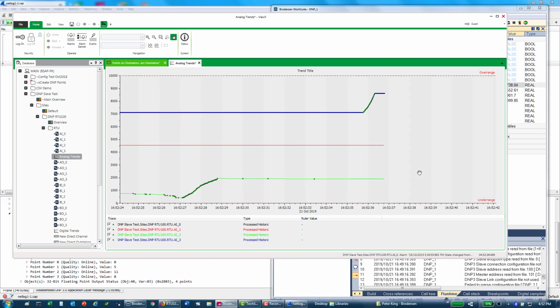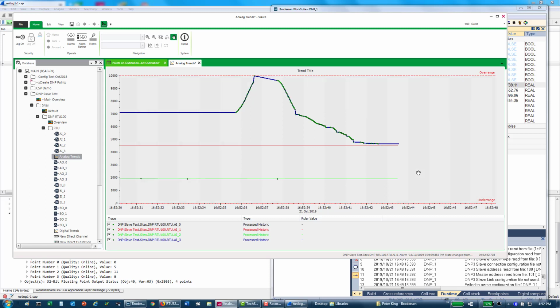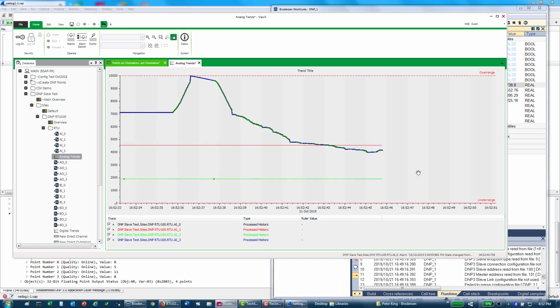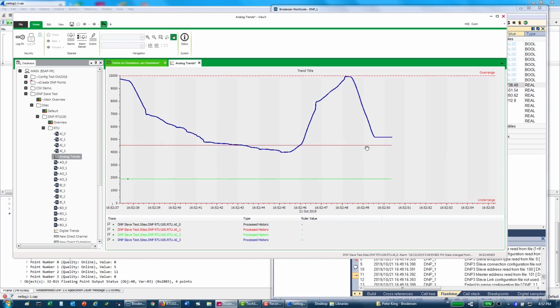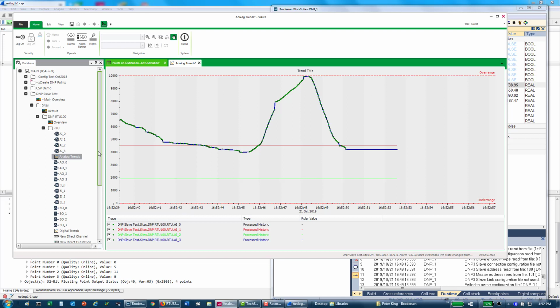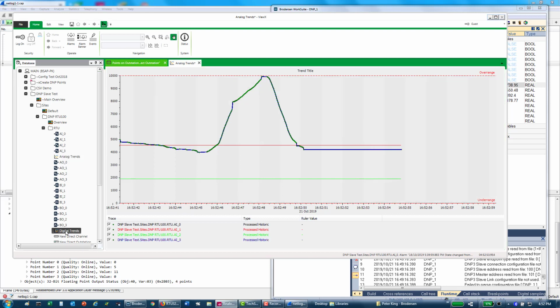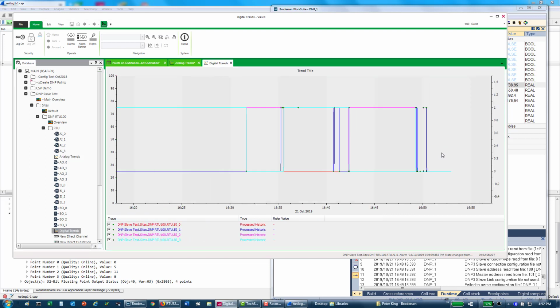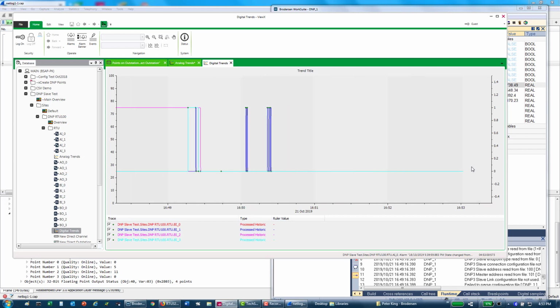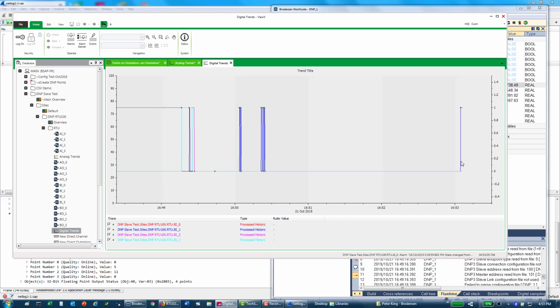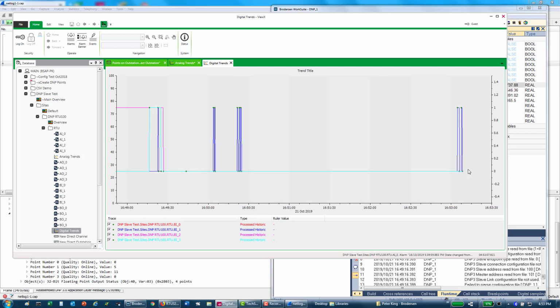If I go to the next guy, just depending, see how there's a little lag before things, but then they get backfilled. So the Class 3 events, we had different rules again. Now the event reporting is easy to see when we look at the digitals. So let's zoom in a little bit. If I change the state of my channel 1, which was a Class 1 event, we see it happening straight away.